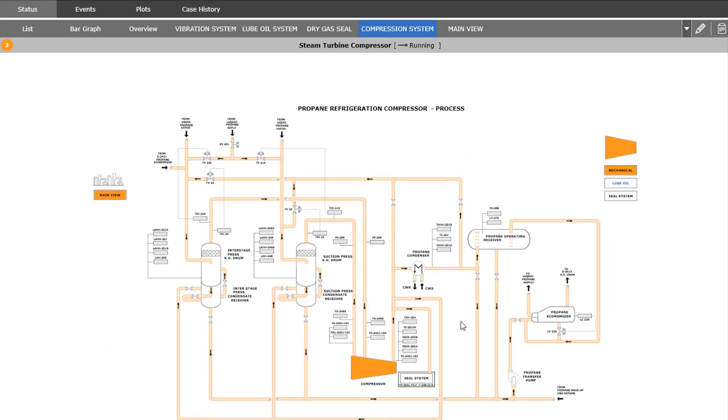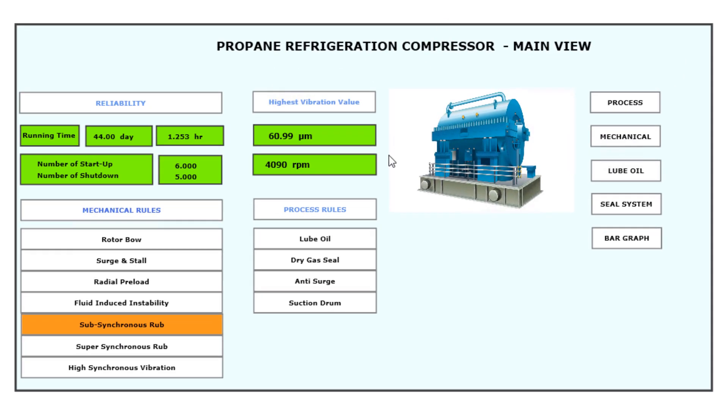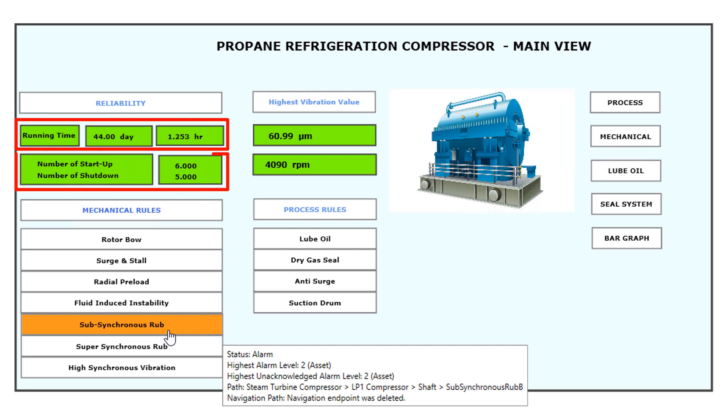The engineer then targets the compressor in alarm and gathers additional insights. The engineer reviews calculated KPIs from System One's decision support, such as running time of the compressor, number of start-ups and trips, as well as the highest vibration from all vibration transducers on the compressor.